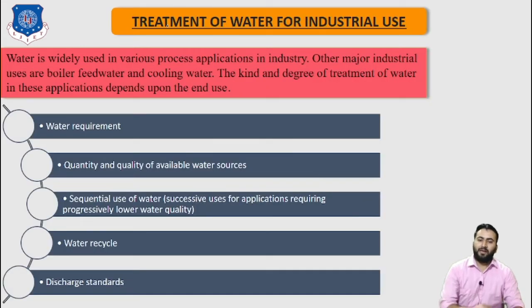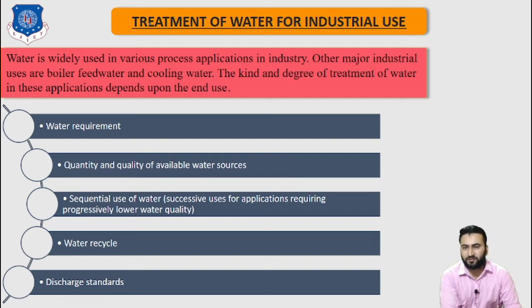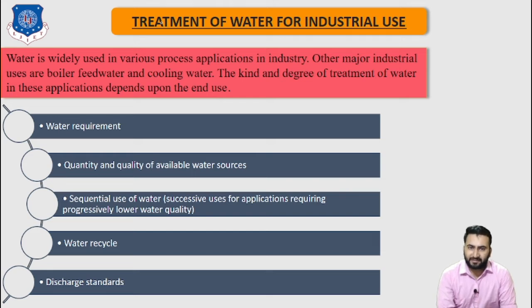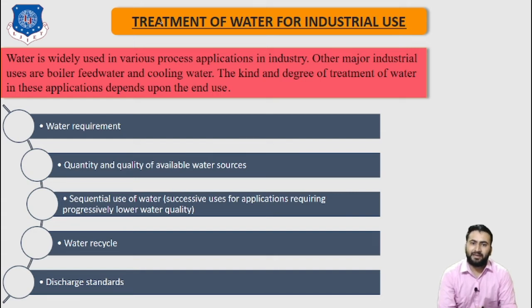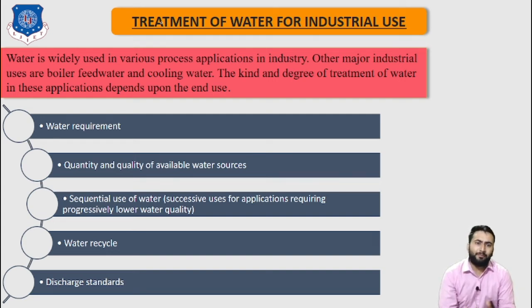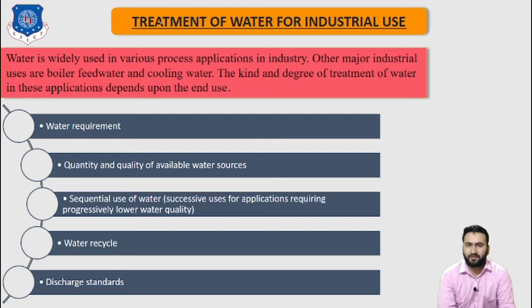Now let's discuss the treatment of water for industrial use. Water is widely used in various process applications in industry. Other major industrial uses are boiler feed water and cooling water. The kind and degree of treatment depends upon the end use of that water. For example, cooling water may require only minimal treatment, while removal of corrosive substances and scale-forming solutes is essential for boiler feed water.